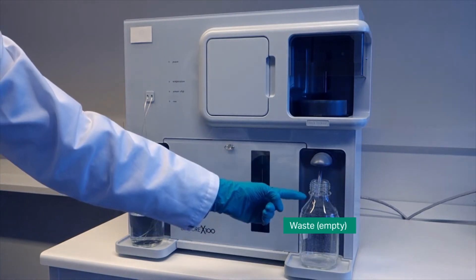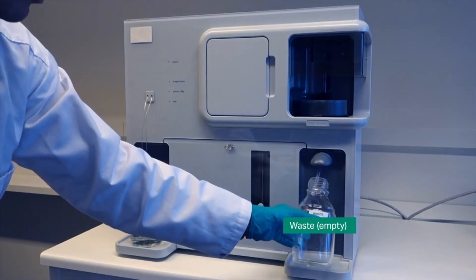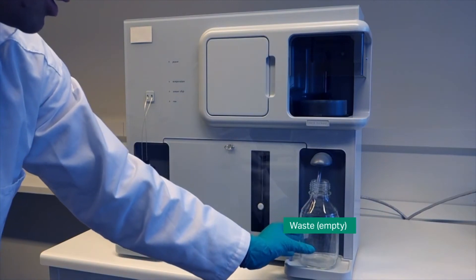Ensure that the waste bottle on the right hand tray is empty and the waste tube is inserted in the neck of the bottle.